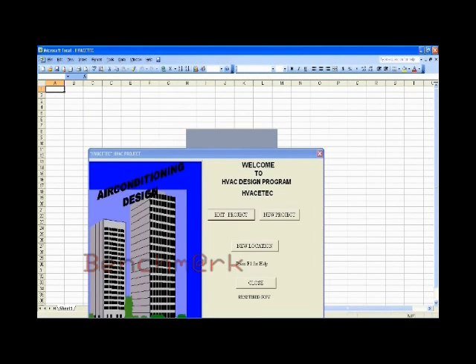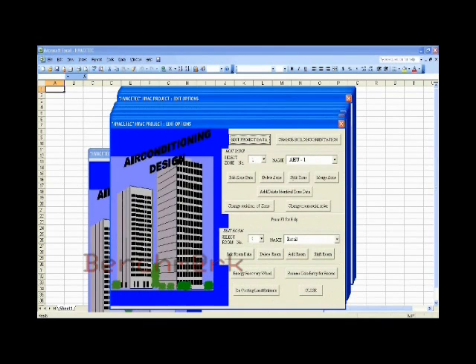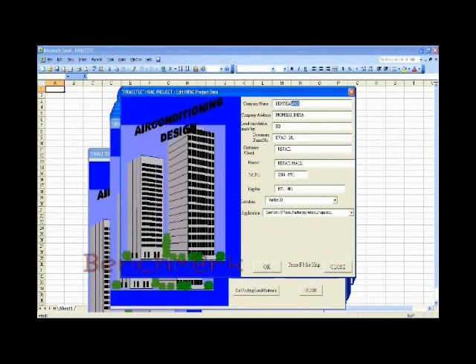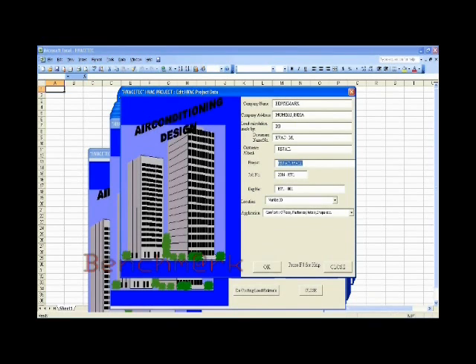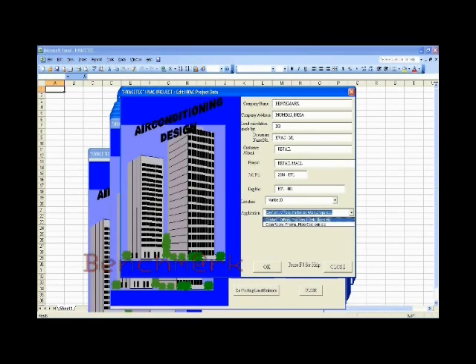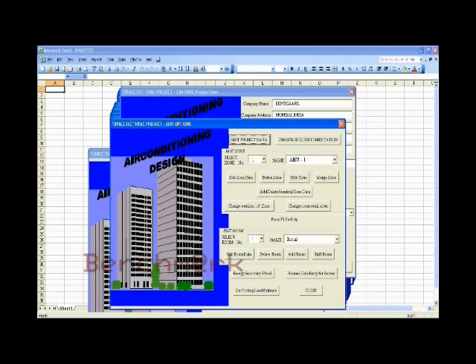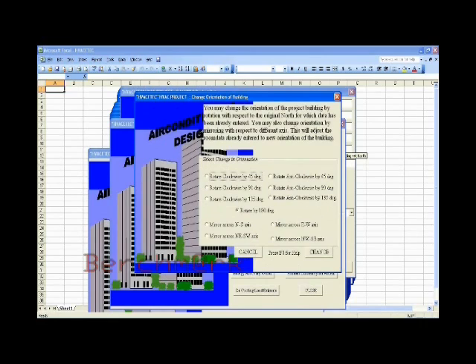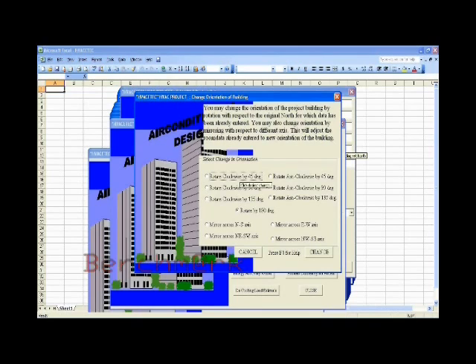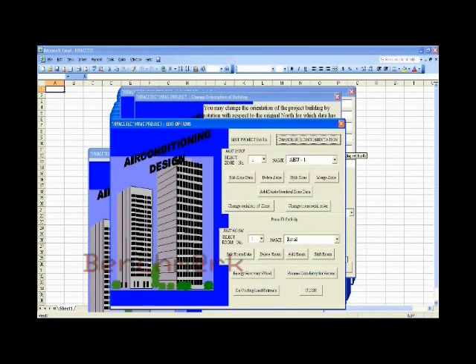So let us input the data: company name, company address, load calculation done by person name, document name, customer client name. In this case we have retail, project name retail mall, job number, drawing number, location Mumbai. We are doing as per the design conditions, application will be comfort. This software can also be used for clean room application. Now come to the orientation of building. You can change the orientation as per your building. We have seen north direction in our architecture plan, so we will proceed with the same.